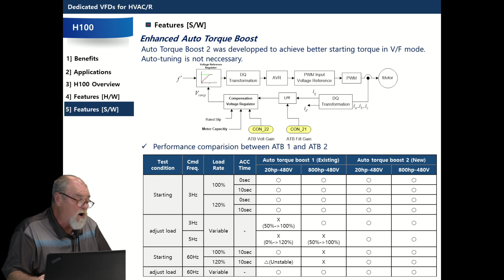We've improved torque boost. That's great for some of the larger pump stations. I've done several of the large 500 horsepowers with long runs that require that additional torque to overcome the head, the check valves, the flaps.